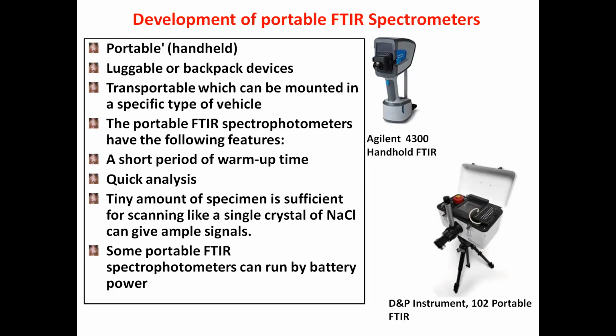Portable FTIR spectrophotometers have the following features: a short warm-up time is required in comparison to a traditional FTIR. Quick analysis is possible. A tiny amount of specimen is sufficient, a very small amount. For scanning, like a single crystal of salt, NaCl, that will give you ample signal about that material.